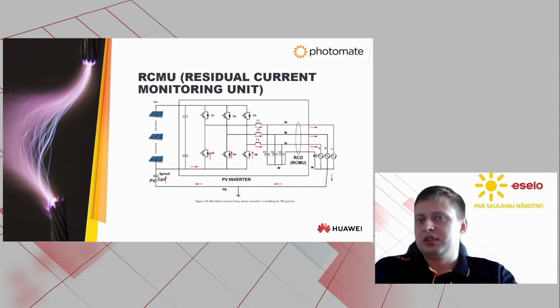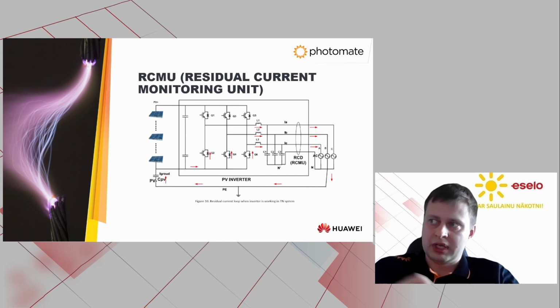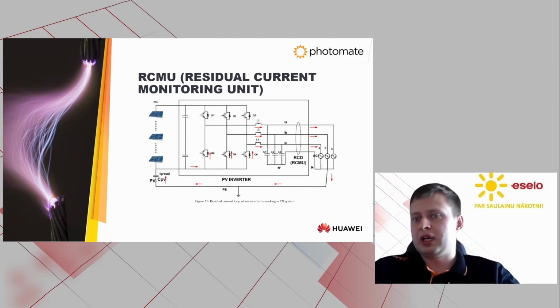In a low voltage distribution network, residual current can pose a potential hazard to electrical equipment and people. As shown in figure 10, the residual current loop can be affected by the type of the network. A TN system experiences higher residual current than an IT network. It is because TN systems have a direct connection to the ground, and because inverters are usually transformerless, the current loop flows around through the AC to DC side and closes the loop through the ground.